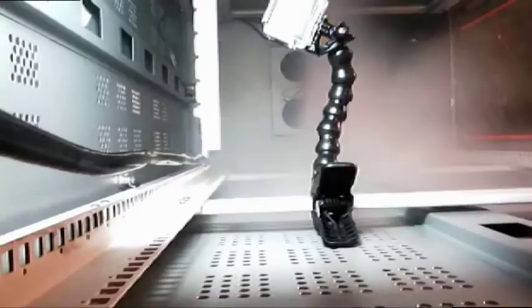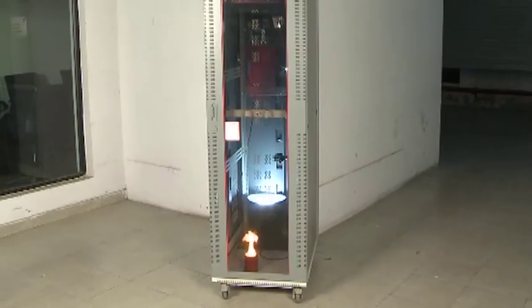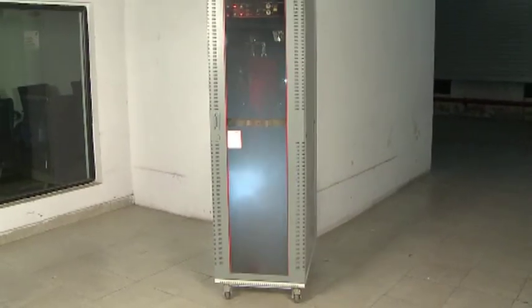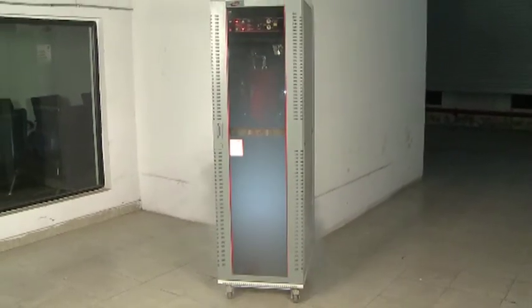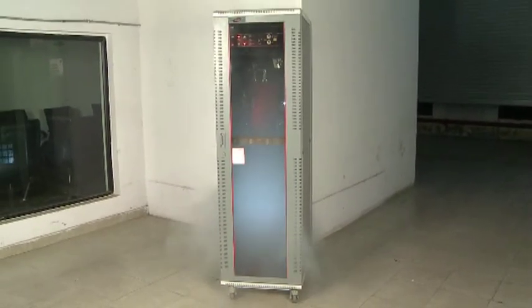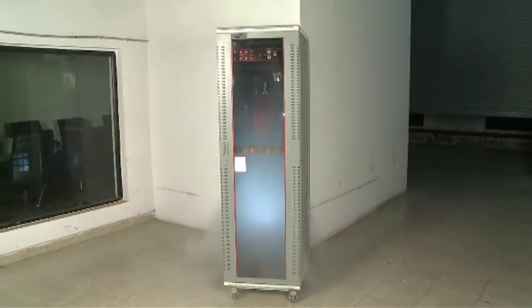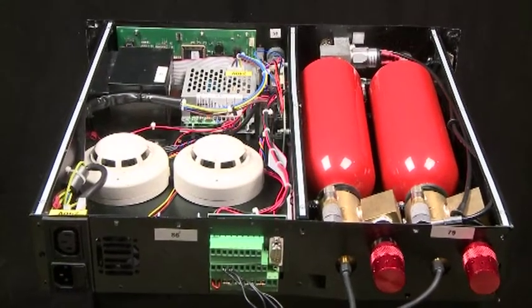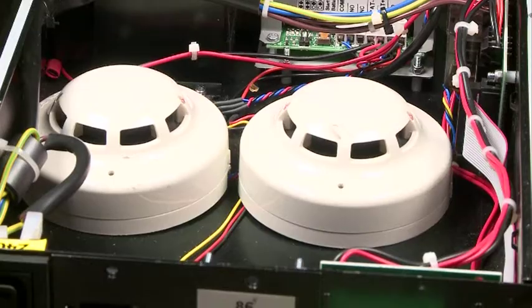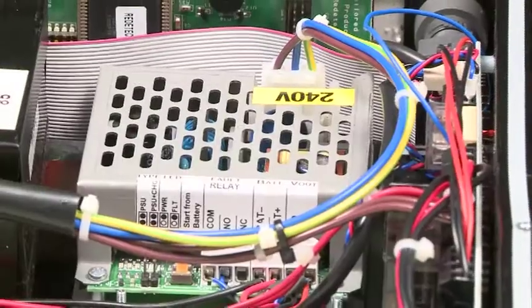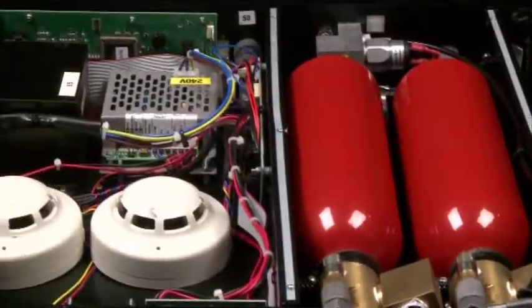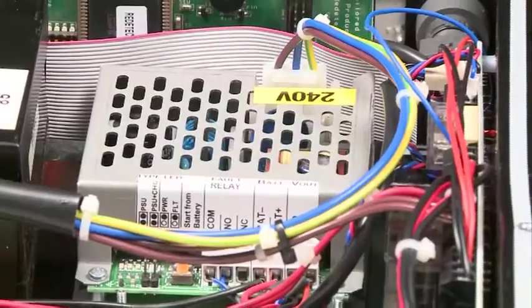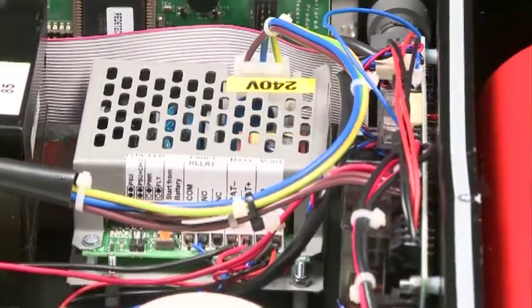The extinguishing agent HFC-227EA is discharged. As it activates, a hooter goes off, warning personnel about the fire. All components of the system, including the detectors, control signals, extinguishing agent cylinders, and alarm devices, are all packed together as one compact modular unit.